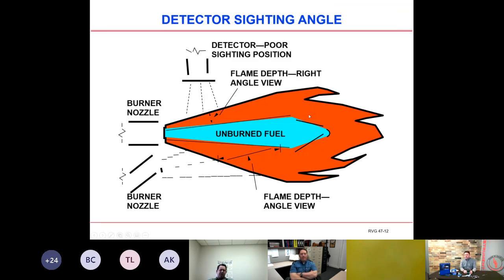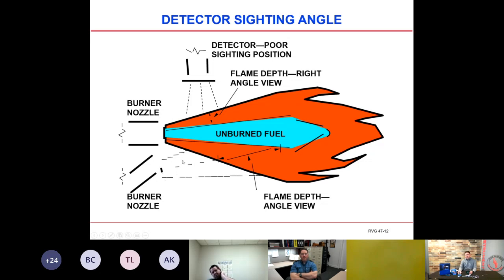Proper viewing angle is very critical. You never want the detector viewing straight down at the flame — as shown in the diagram, you have a very short window of UV detection in that orientation and will also run into problems if using a self-checking detector mounted that way. The correct orientation for a mini peeper or C7035 UV detector is coming in through the side of the burner at an angle, picking up about the first 30% of the flame where a lot of UV light is emitted.